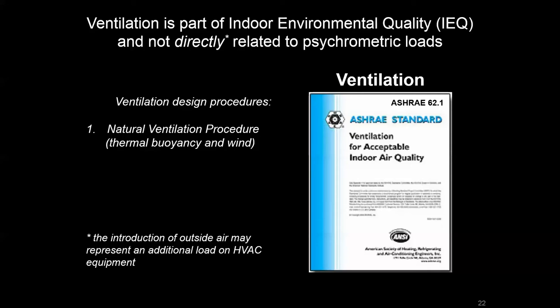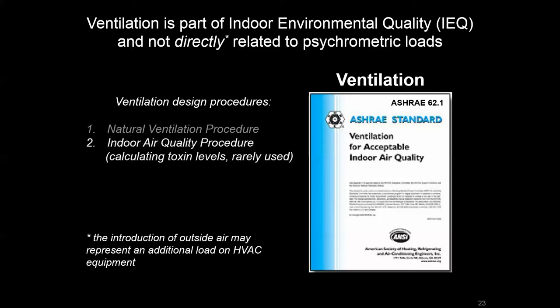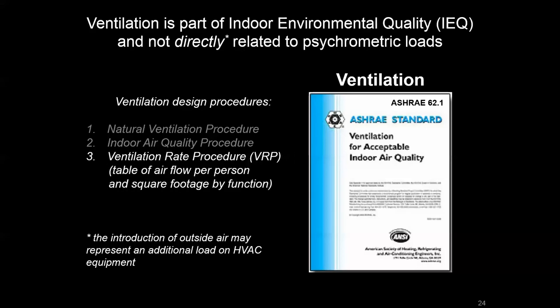Natural ventilation works by understanding how air moves from outside through penetrations and naturally takes hot air out of the building. There's also a way to calculate toxin levels directly and determine how much fresh air needs to be introduced — that's the indoor air quality procedure, which is also rarely used and more applicable to specific lab or manufacturing environments where you have a good understanding of toxin levels. The third procedure, which drives most ventilation design, is the ventilation rate procedure, or VRP.